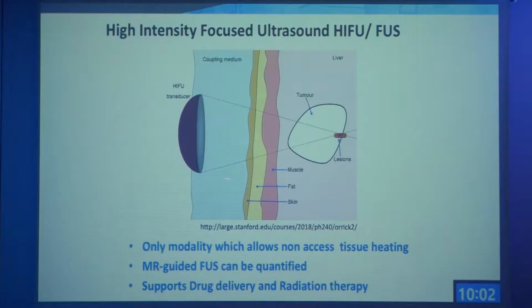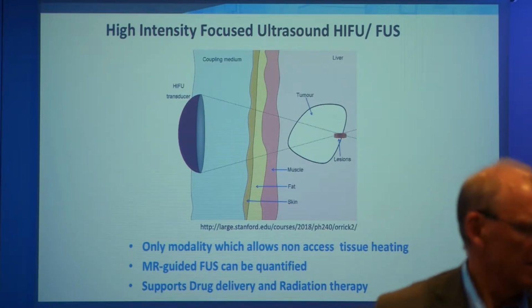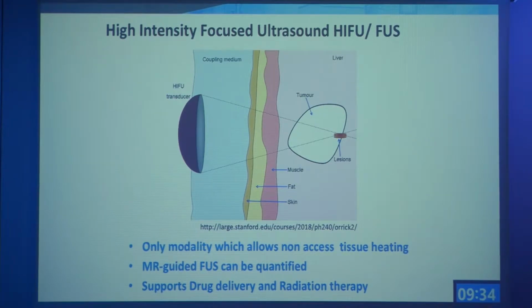The transducer focuses this ultrasound wave inside the tumor tissue, and the healthy tissue around it, and also the skin and muscles, will not be damaged. We only create a very tiny spot with high energy. What is important here is we need to know where the focus point is. That's why we need the MR image to guide the positioning of the focus point. And also, we need to measure the temperature in a non-invasive way. MR imaging gives the possibility.